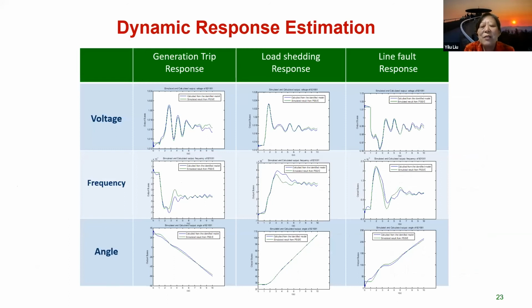We found that the power grid's individual location phenomena are very nonlinear, but the large grid can behave very linearly for a single generator trip. Because of that, we represent the power grid as a transfer function, enabling adaptive damping control where we can monitor the grid and design controllers fairly easily, approximating it as a linear system for small phenomena. Even a 1,000 megawatt generator trip is considered a reasonably small disturbance to a grid, and the grid is designed to deal with that easily.